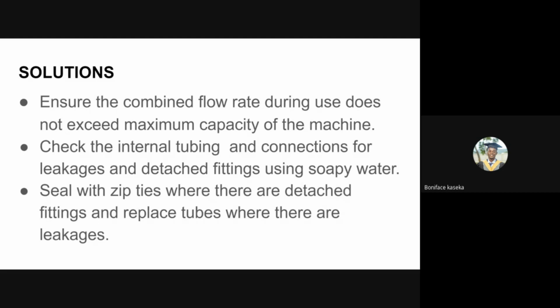If you have, for example, bubbles appearing where there's a connection or a tubing, it simply means that there's leakage right there. So you need to fix that. If you see a connector somewhere, we normally use zip ties. We use the zip ties and make sure that it is tight. And if you apply the soapy water and no more bubbles are appearing, then that means it's okay. But if it's a tube which has problems, then you just need to replace it with a proper one.